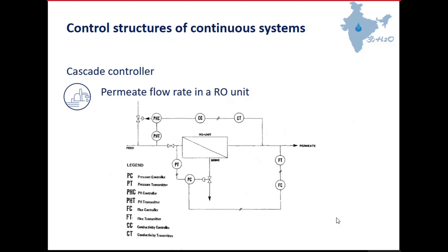Cascade controllers are very useful in reverse osmosis units — for example, when you want to control the permeate flow rate. Here you have a flow transmitter measuring the flow. To control this flow, you can act on the pressure at the inlet, and this inlet pressure is at the same time the set point of a controller that acts on a valve that changes the pressure. This valve changes the pressure and produces a change in the permeate flow.